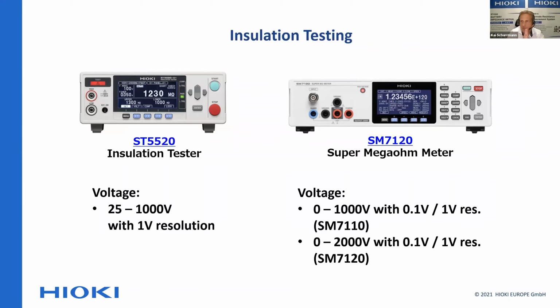I know of one customer in Europe where 2000 volts isn't enough. They're actually using a test voltage of 4 kilovolt for the cell insulation, but that really is the exception. The vast majority of people are using the ST5520 with a voltage typically around 500 to 1000 volts as a test voltage.